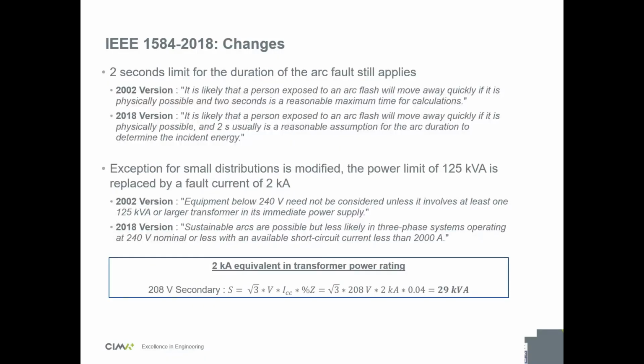Now there's a concept called the 2-second limit. As a basic reminder of arc flash, the energy is proportional to the fault current squared times the fault clearing time. The fault clearing time is the time it takes for the upstream protection to clear the fault and stop the arc flash. The 2-second limit means that within 2 seconds, you consider that the worker has time to move away from the source of the arc flash.